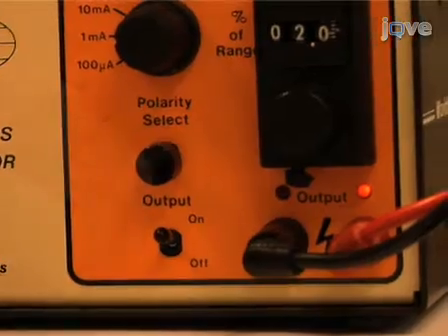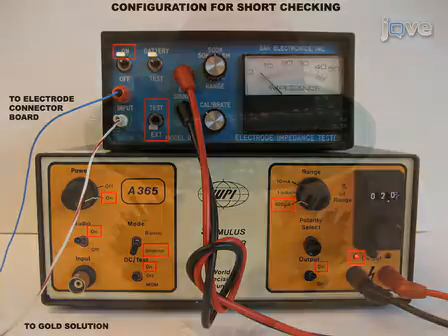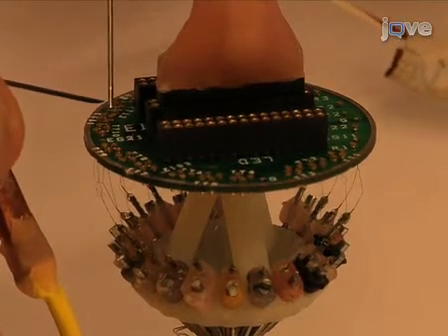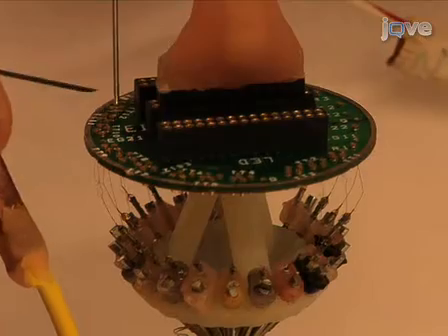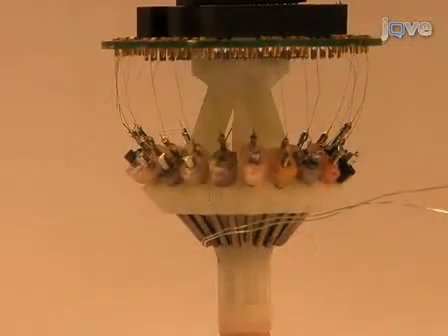Gold plating the nichrome tetrodes is critical for long-term stable recordings. It prevents corrosion and improves biocompatibility. Set up the impedance meter in external mode and the current generator in DC check mode with audio output. Touch the two leads of the current generator to the six possible pairs of channels within each tetrode and use the audio feedback to determine if shorts exist between pairs. A short between channel pairs sounds like this. If a short exists, recut the tetrodes with serrated scissors and test again. If the problem persists, discard the tetrode and replace it. Move all the micro drives down, extending all the tetrodes as far out as possible.